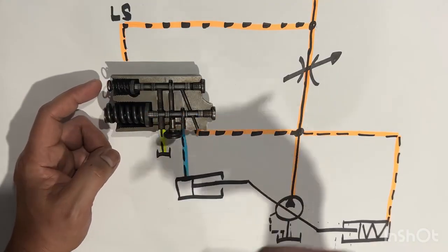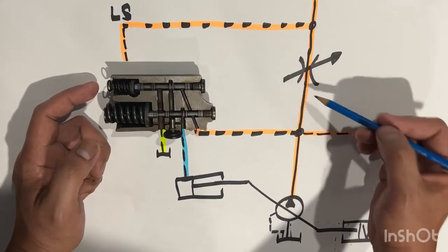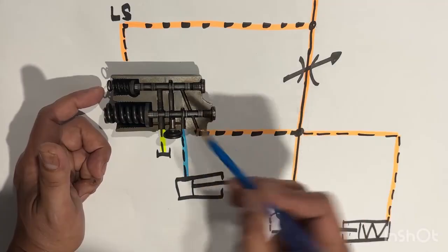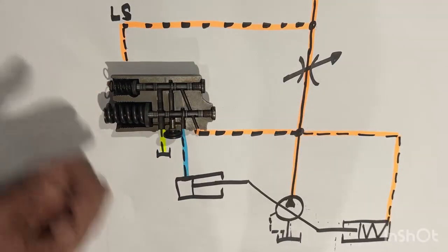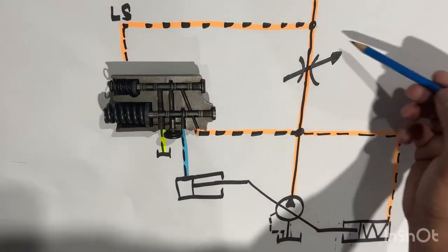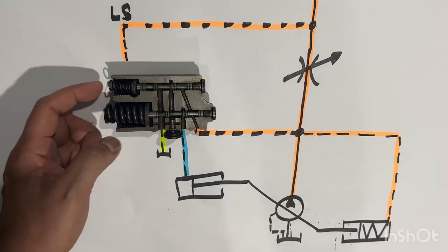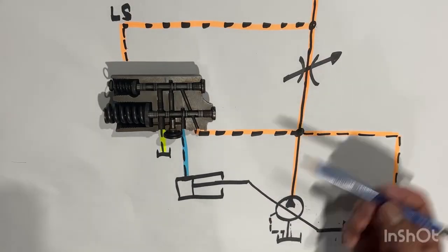Okay, so changing the throttle position, this one here, which acts as a control valve, will vary the flow necessary to maintain the differential spool spring preload, this one here, which is the 15 bar. Okay, the pump will automatically vary its stroke to maintain the load sensing pressure drop constant. Okay, so if you have 15 bar delta P, it will maintain 15 bar delta P.